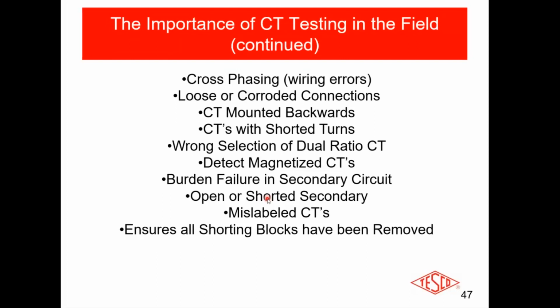Ensuring all the shorting blocks have been removed. Typically, the last thing you do after you put in a new installation is you pull out all the shunts, right? You remove the shunts. And if you don't, what happens? You're not really using those CTs. You're not getting any real energy measurement at your meter.